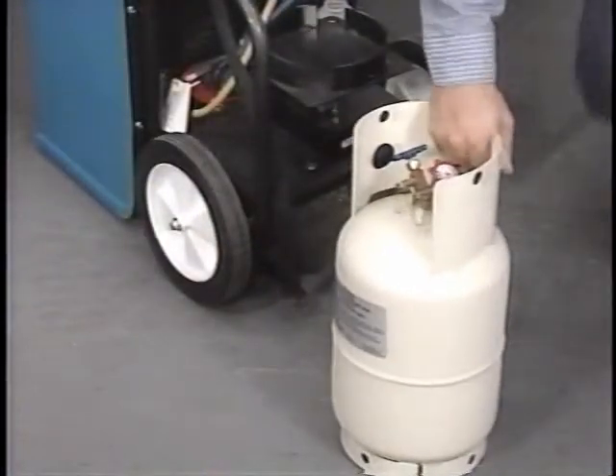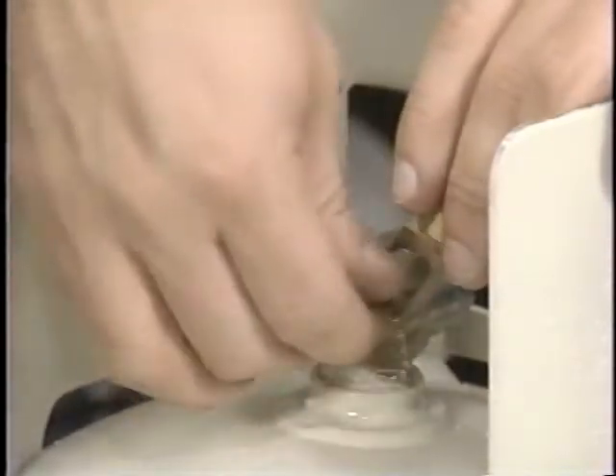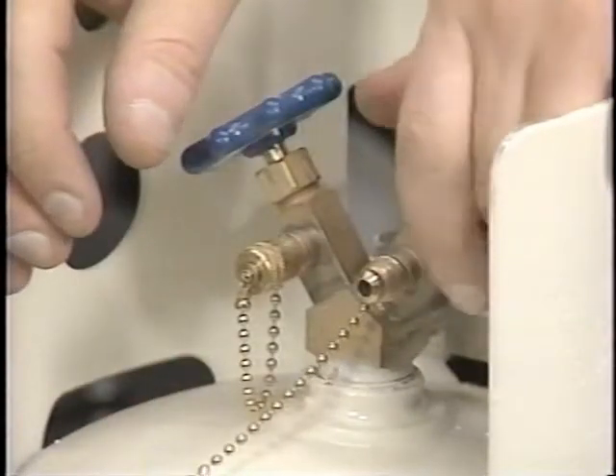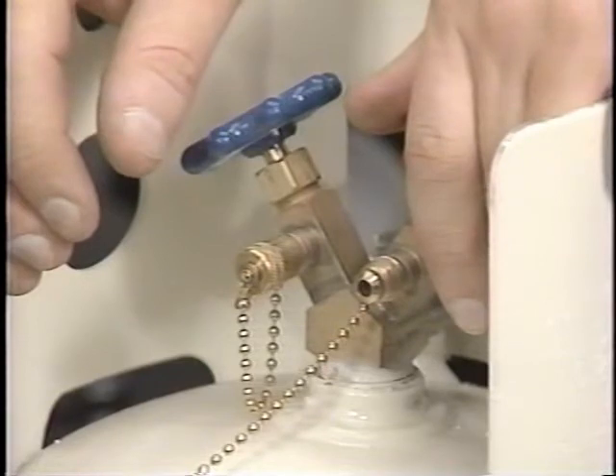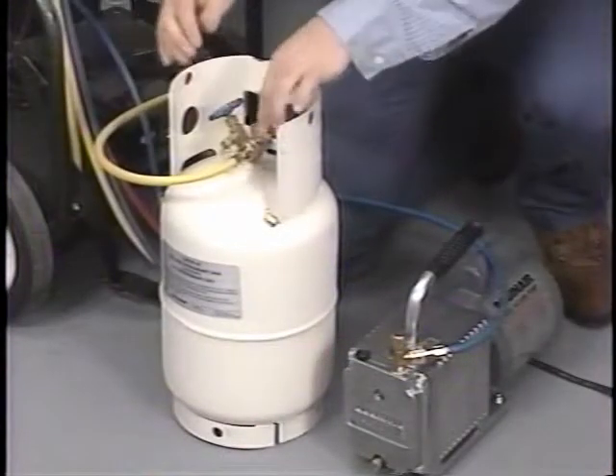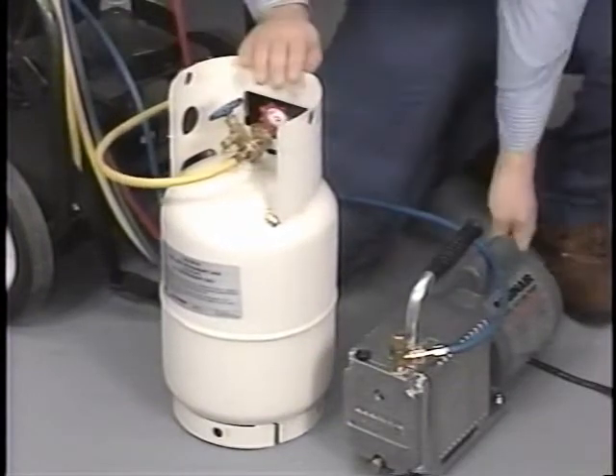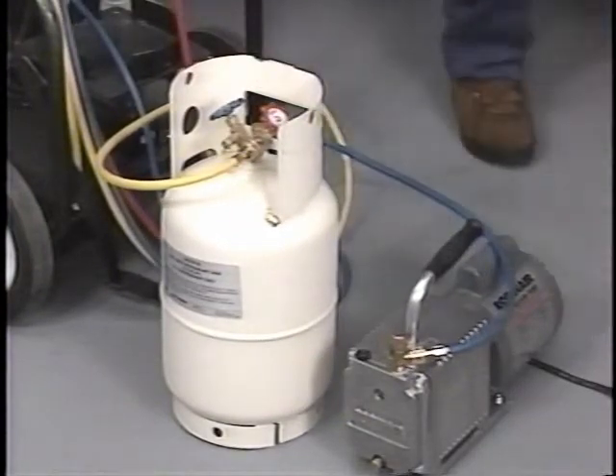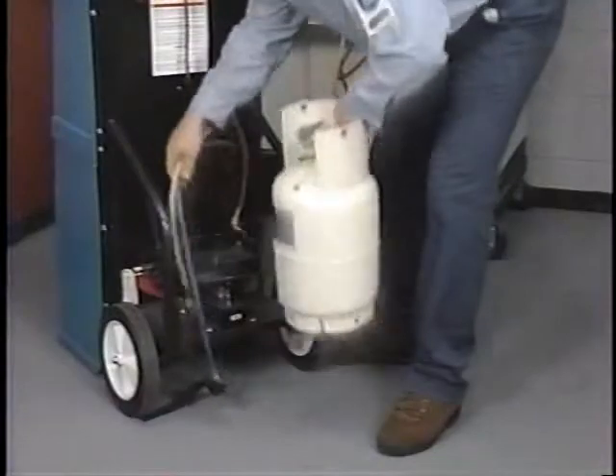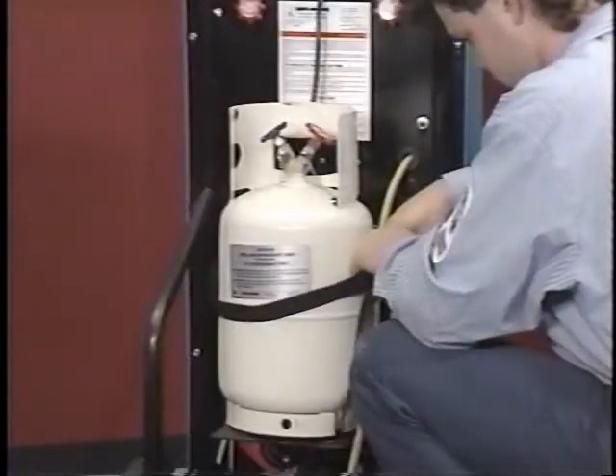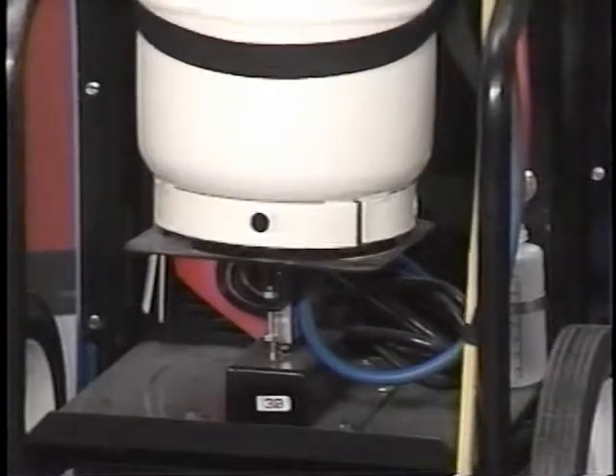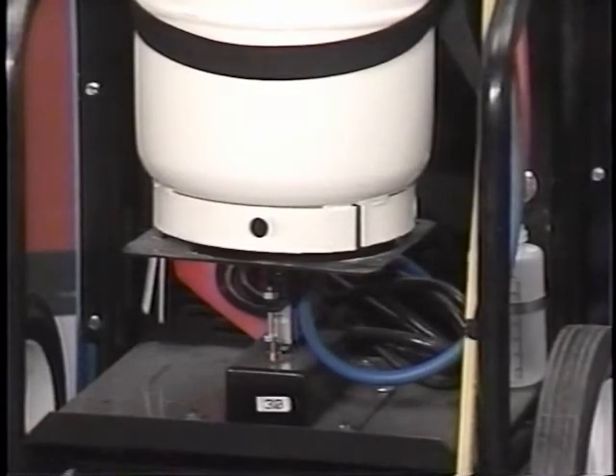The new tank contains dry nitrogen. Slightly open the gas valve to bleed off pressure. Don't worry. Nitrogen is a harmless common gas. In fact, you're breathing it now. When the tank is empty, evacuate it with a vacuum pump for about 10 minutes. Set the tank on the platform. Attach the strap, but not so tight that it stops the platform from moving.